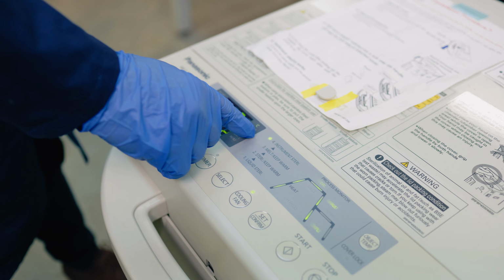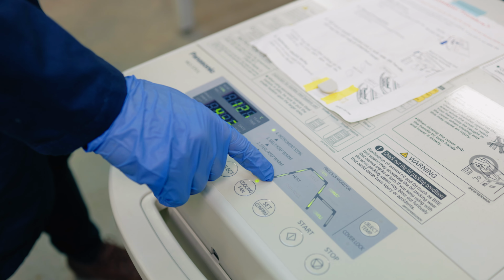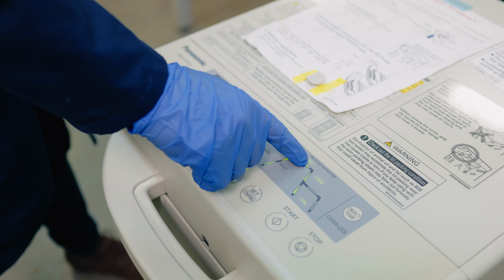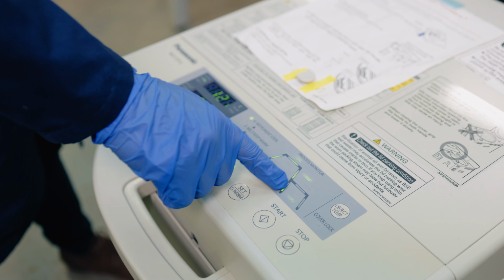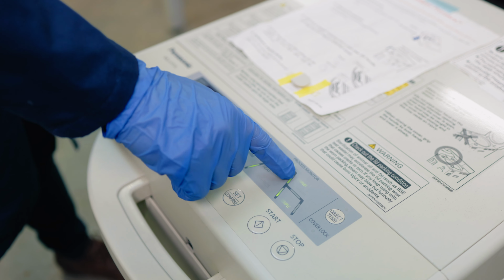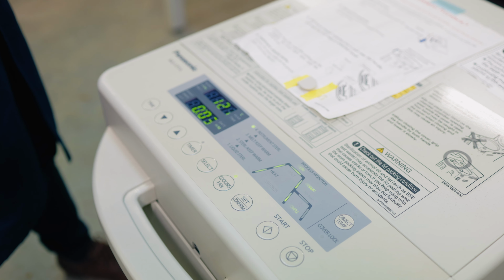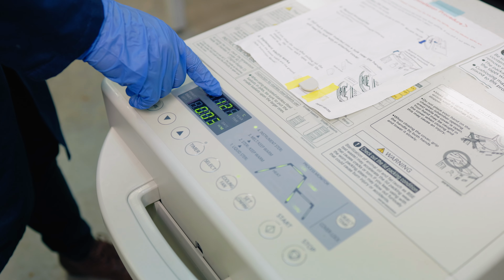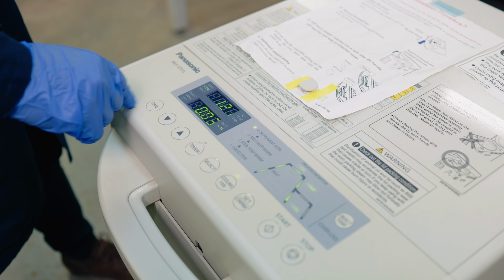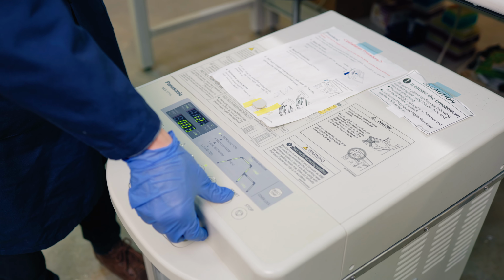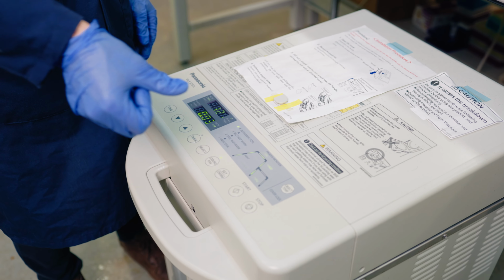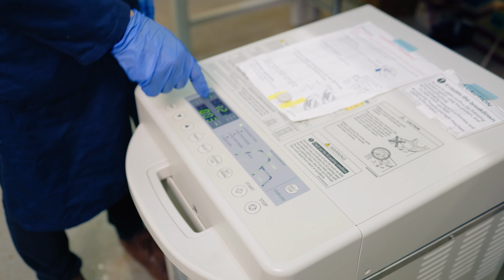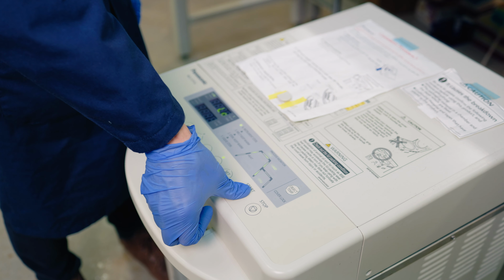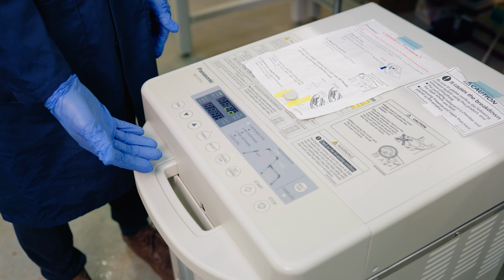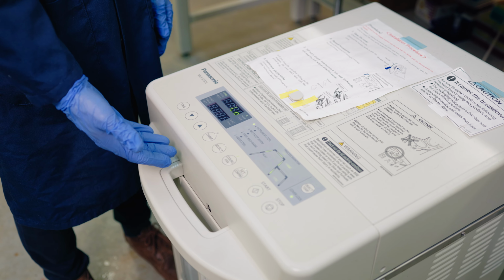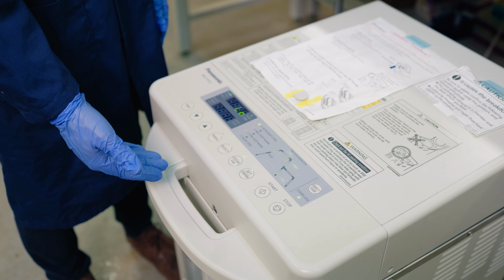And you can hear her describing the different programs, and for each one it tells you what it does. This one heats up, sterilizes for a while, and then it doesn't hold at a warm temperature, it just cools it back down. It specifies the temperature that it's going to go up to, some other details. I'm going to go over and press the start button. You have to kind of do a long press. It'll start blinking, and then you long press it 1 more time. And you can hear it say the instrument sterilization program is running.